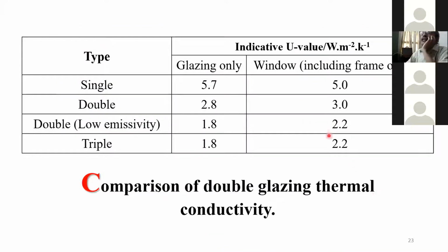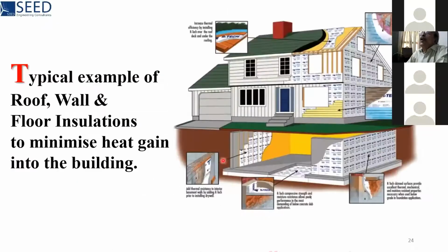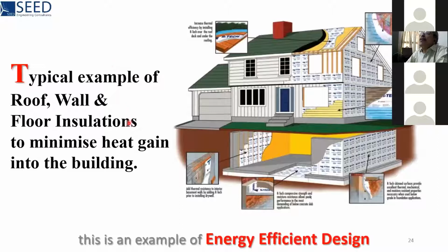Just to give a comparison between the U values, in watts per meter square per degree Kelvin. For the glazing only, single is 5.7, double 2.8, double with low emissivity 1.8, and triple 1.8. For a window with frame, single is 5, double is 3, double with low emissivity is 2.2, triple is 2.2. You can see how much heat gain into the building can be minimized by using better construction materials. Good quality insulating materials are now available in the market.